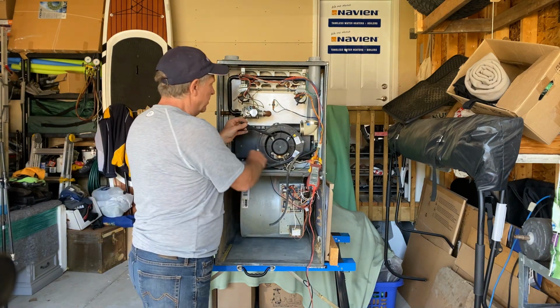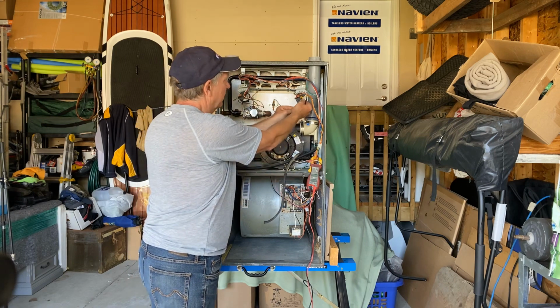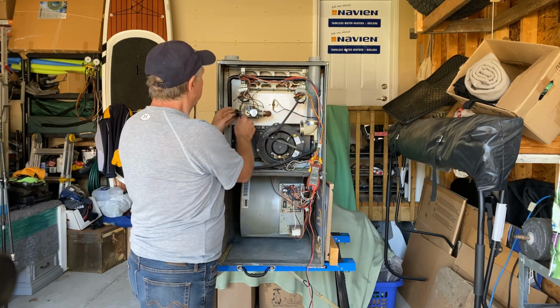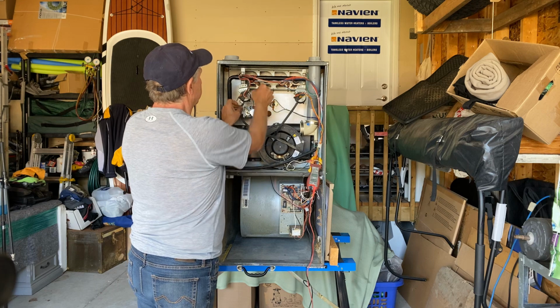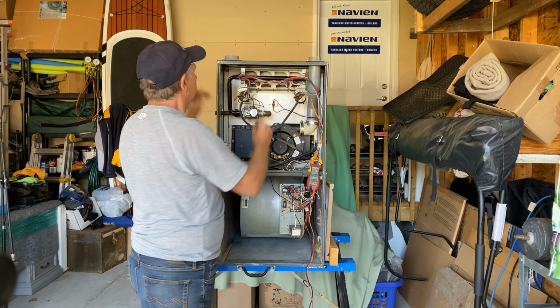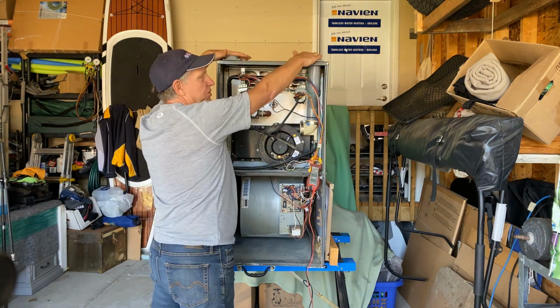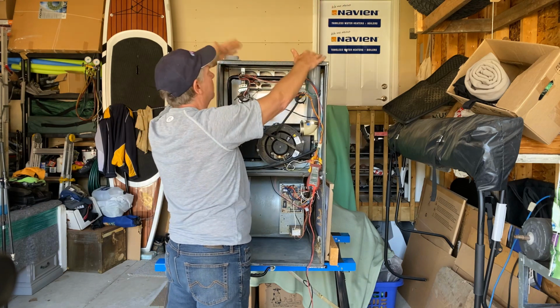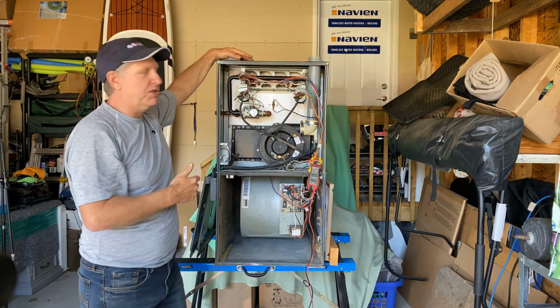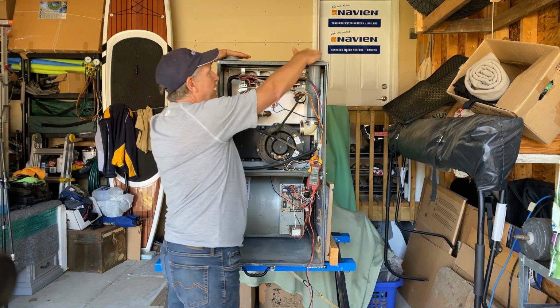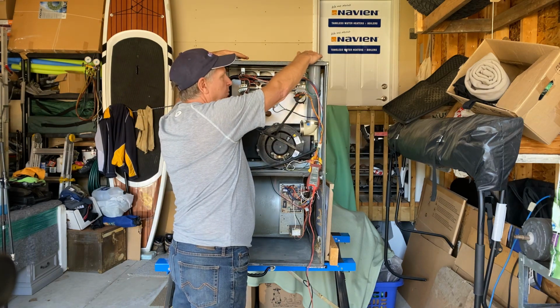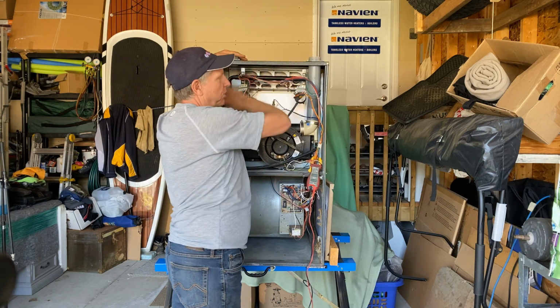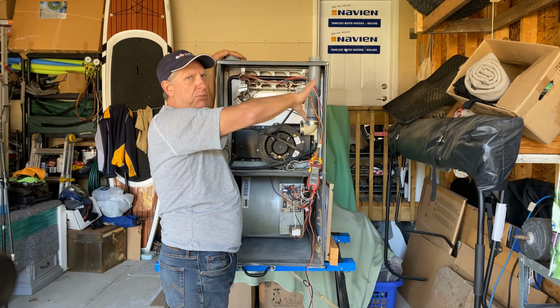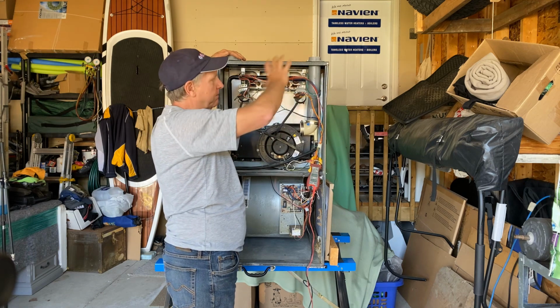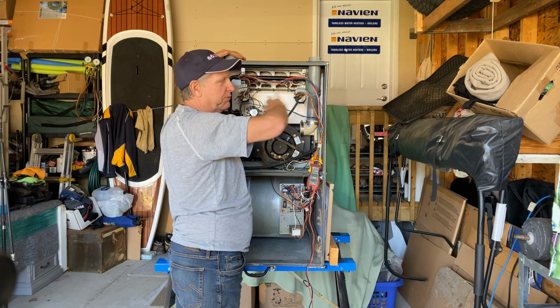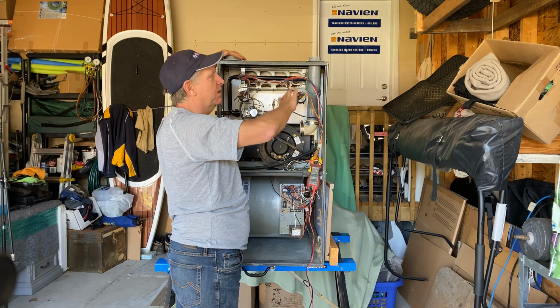These pressure switches, I mentioned that before. Their function is, if you've got your vent connections here, your exhaust going out, your combustion air, fresh air coming in, if for any reason any of these was plugged, your burner's going to be messed up terribly. Your flame's going to look really bad. Your heat exchangers are going to plug up. There's going to be sooting. There's going to be all kinds of problems.